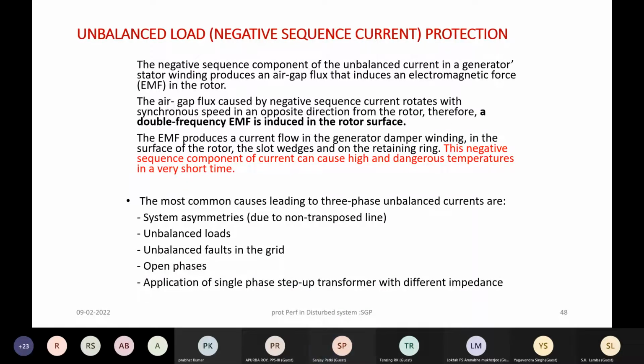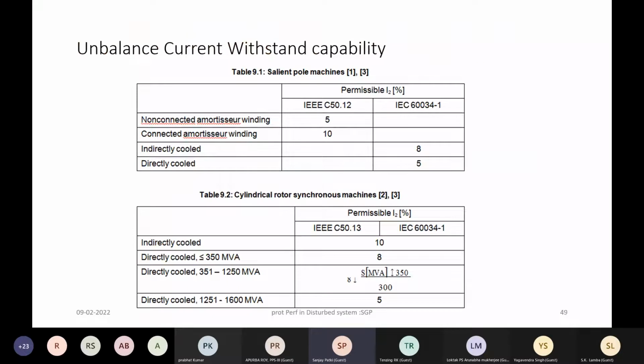Unbalanced currents. Sometimes not so much for hydro units, but this unbalanced load negative sequence protection is important for thermal machines, because there is a negative sequence, which is a double frequency component of the current, that can result in excessive heating. So unbalanced protection is another protection which needs to be properly coordinated, especially when there is a disturbance in the grid. And there is guidance provided in terms of the I squared T, I2 squared T characteristic, which defines the negative sequence capability for different types of machines. So this is given here.